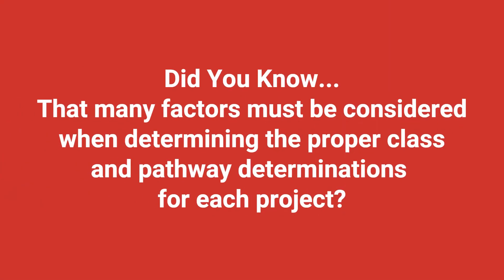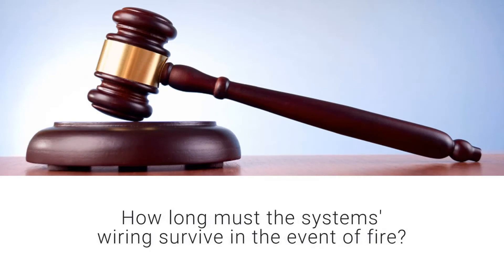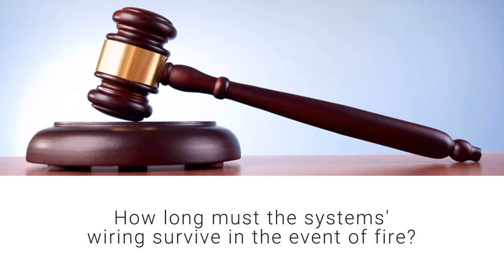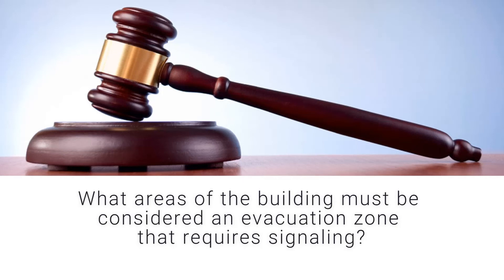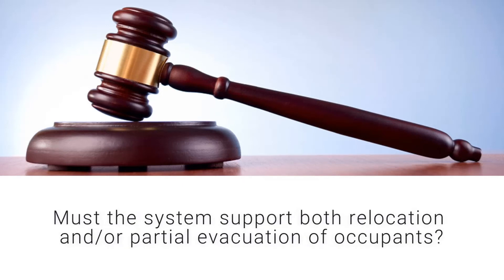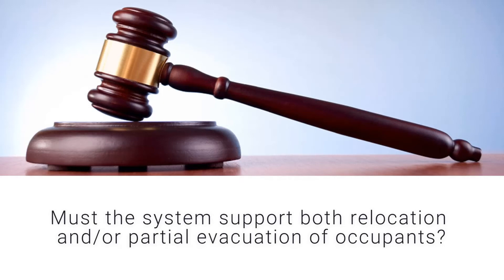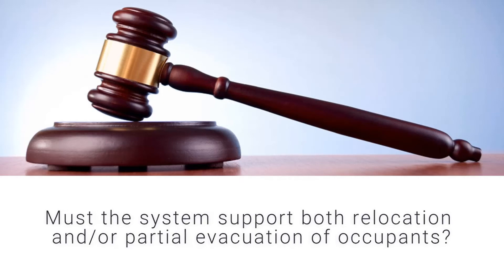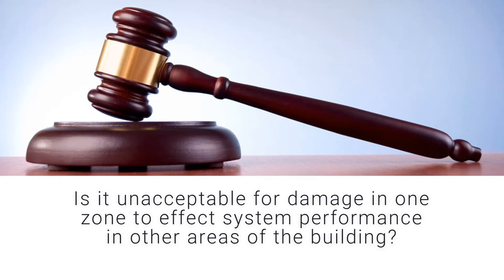Many factors must be considered when determining the proper class and pathway determination for each project, and determination ultimately resides with the local authority having jurisdiction. These factors include: How long must the system's wiring survive in the event of fire? What areas of the building must be considered an evacuation zone that requires signaling? Will both emergency alarm and voice communication be required? Must the system support both relocation and/or partial evacuation of occupants? Is it unacceptable for damage in one zone to affect system performance in other areas of the building?